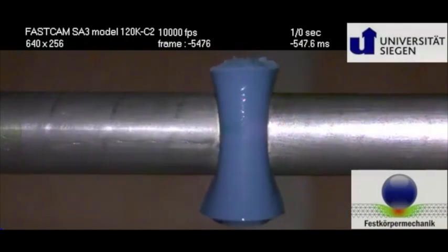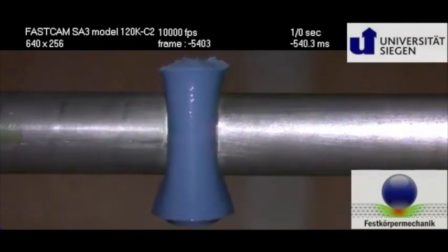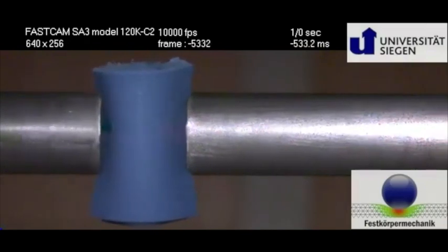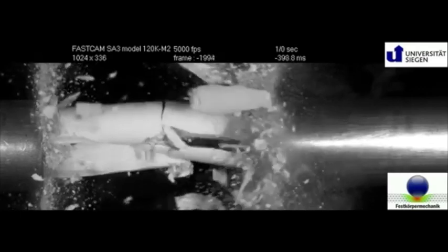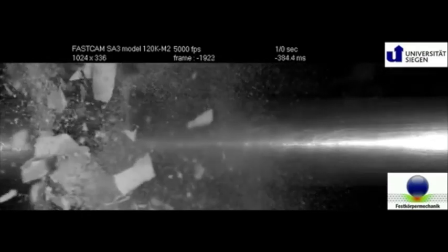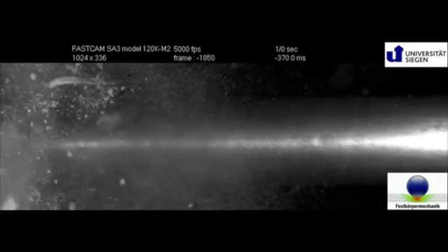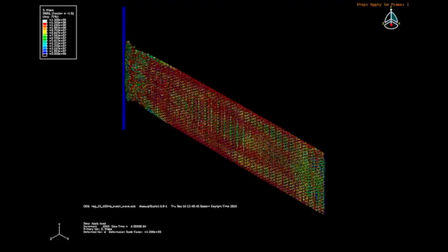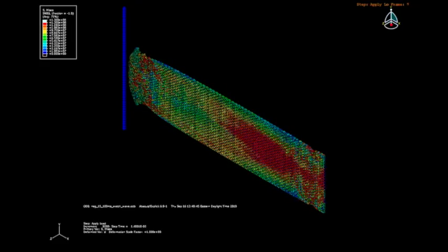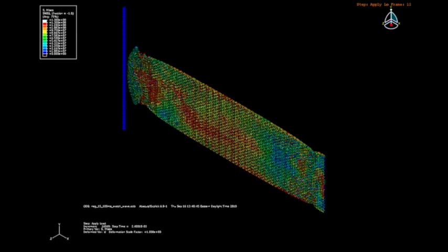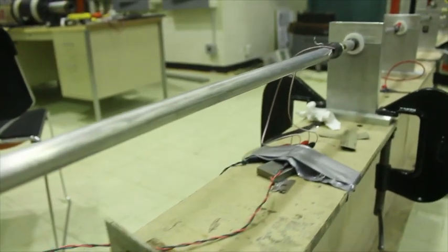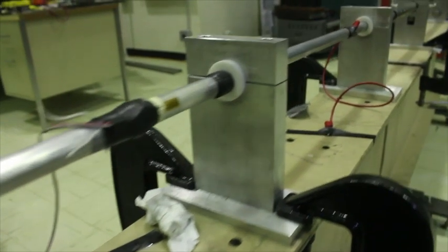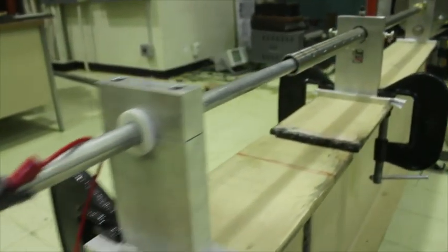The Hopkinson pressure bar was first suggested by Bertram Hopkinson in 1914 as a way to measure the stress pulse propagation in a metal bar. Later in 1949, H. Kolsky refined Hopkinson's technique by using two Hopkinson bars in series to measure stress and strain, incorporating advancements in the cathode ray oscilloscopes to record the pressure wave propagation. Bars of different materials ranging from polymer plastic to steel and aluminum are used depending on the type of material to be tested.